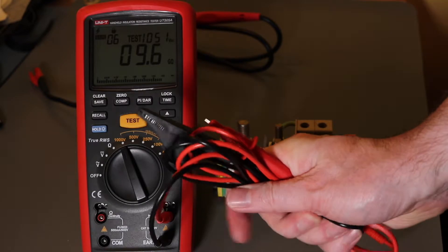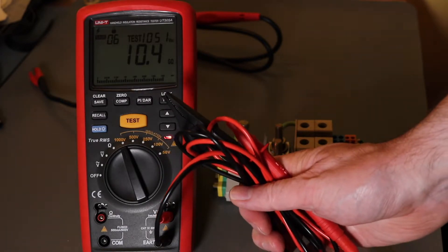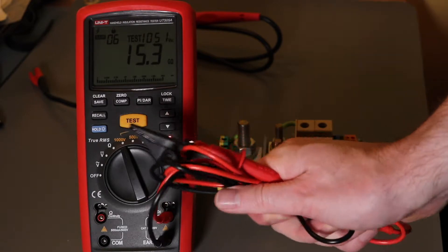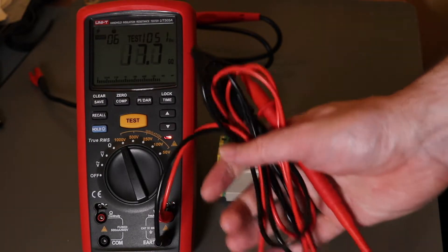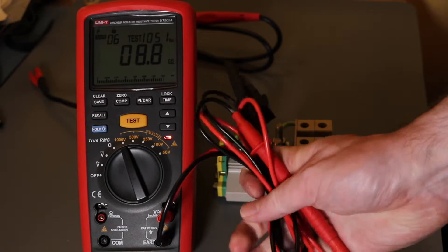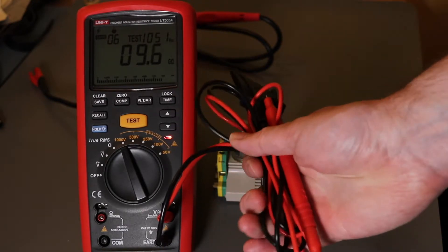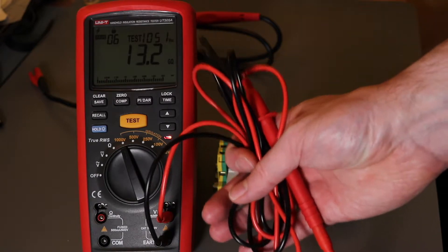So that won't really affect a one minute reading or a dial reading, but if you get into pi ratios and you get up into these high values, that can obviously affect if you had a motor at 20 gig ohms, but your leads are only 10 gig ohms between them. If you happen to trap them or something like that, you'll affect the reading that you're getting.